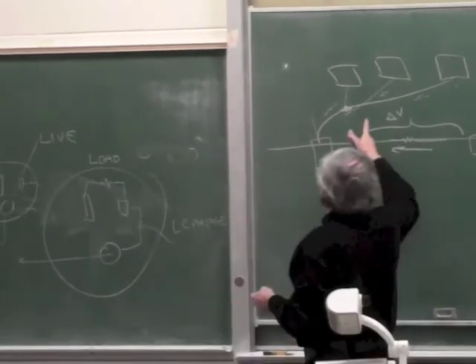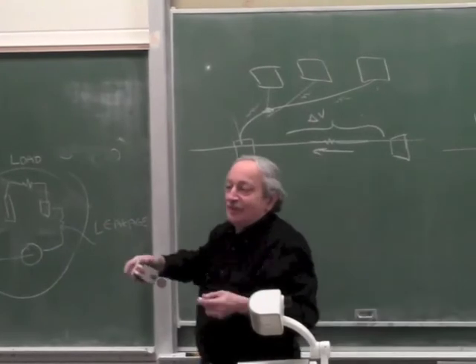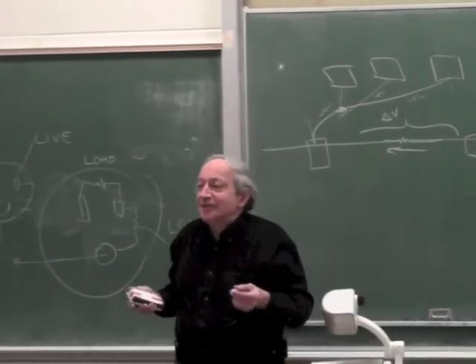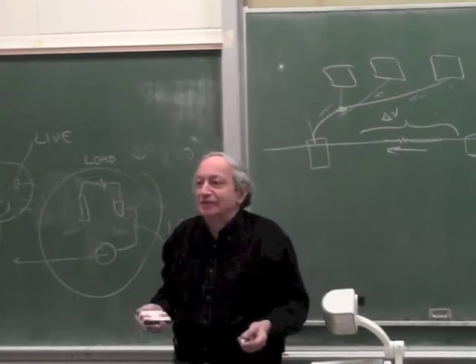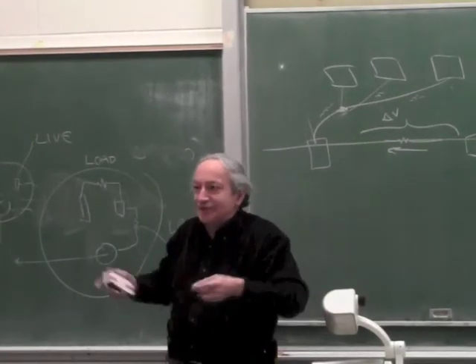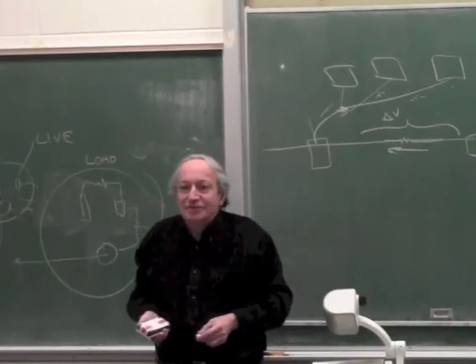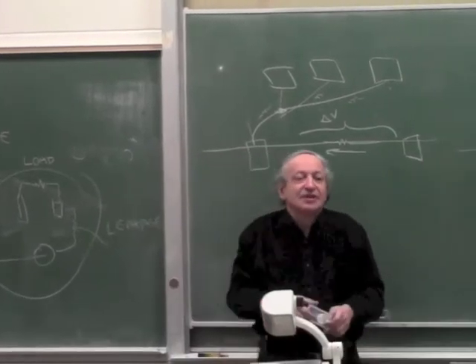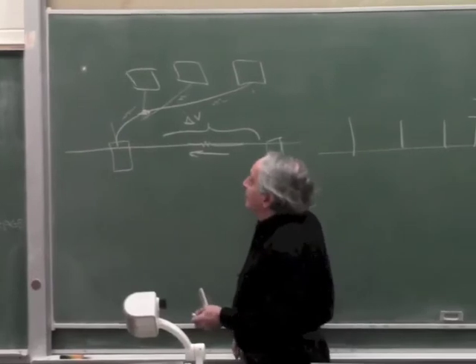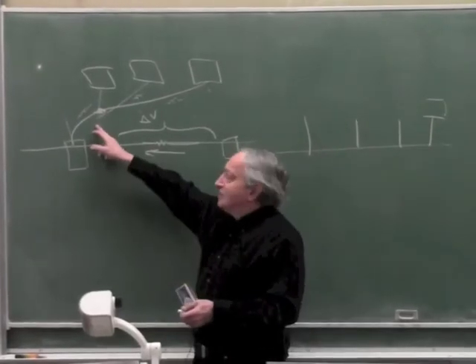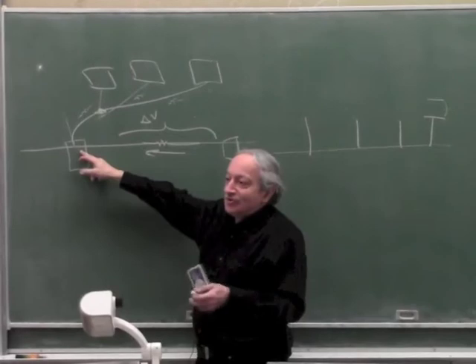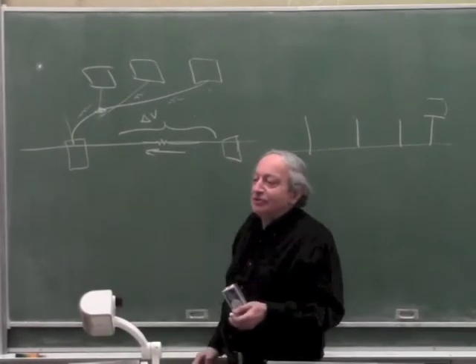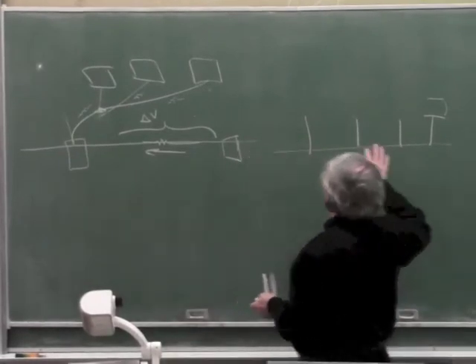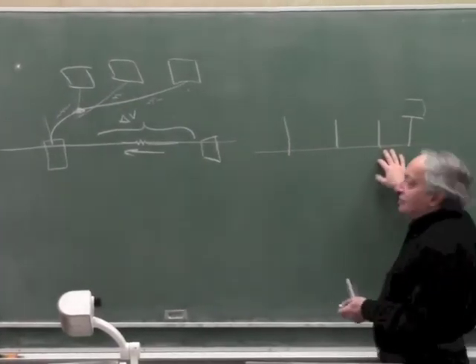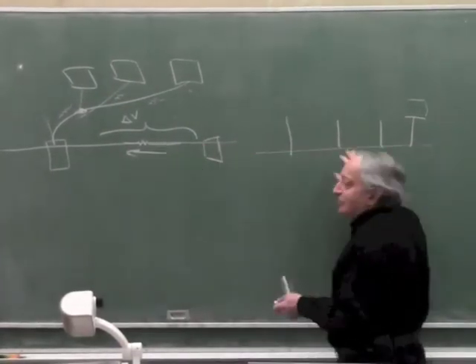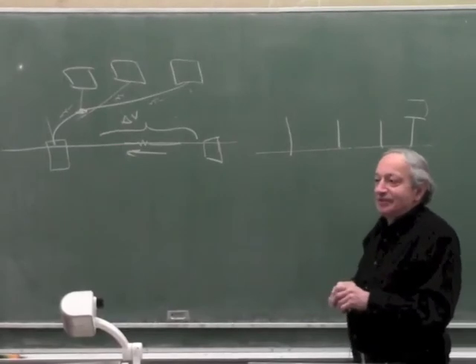If this is a microhenry, but you're working with 100 megahertz, then the ground, even a meter of wire, is a very bad ground because of j omega L—it actually looks like a big impedance. So for low frequency distributed systems, you sometimes may have to do this, called central point grounding or audio style grounding. For high frequency, you don't have the choice—you have to do this, while in low frequency you have a choice. You can do this or this, depending on the circumstances and what's most appropriate.